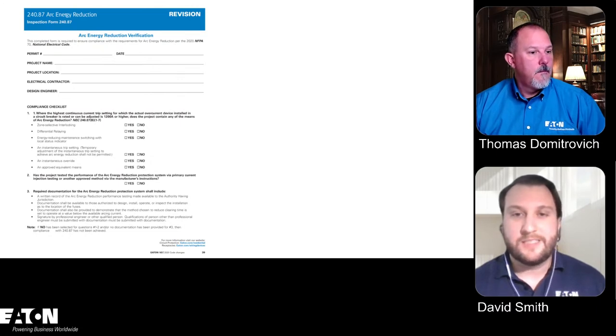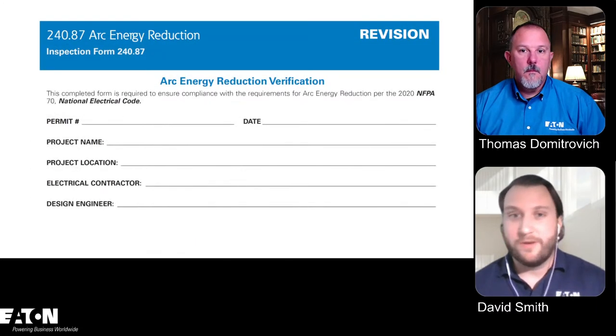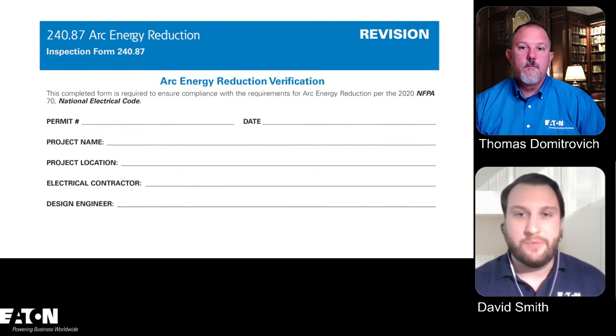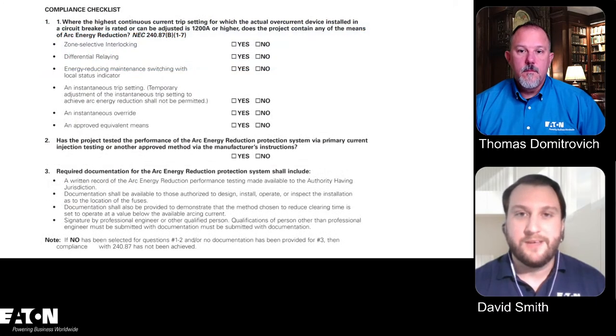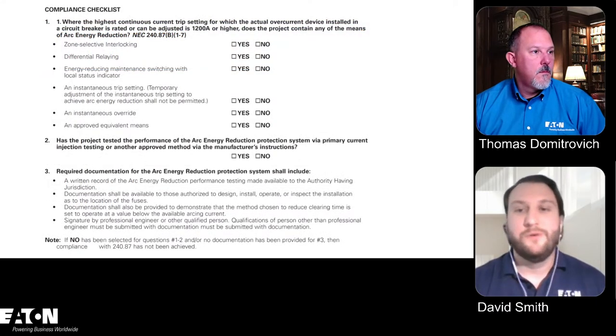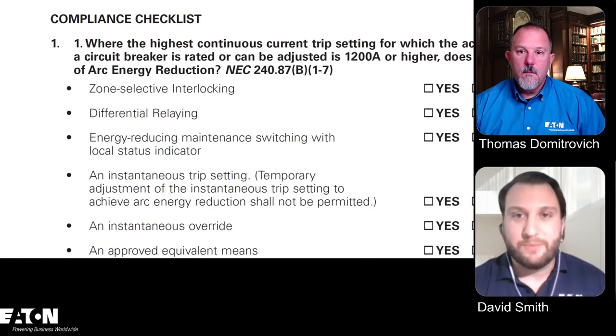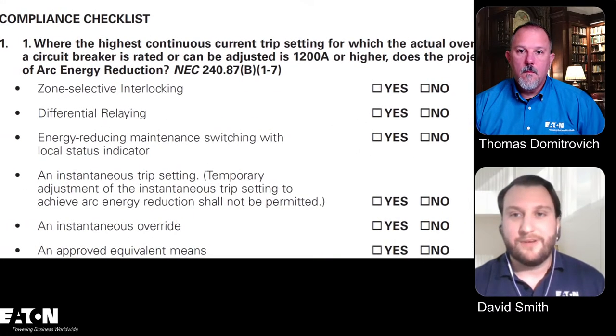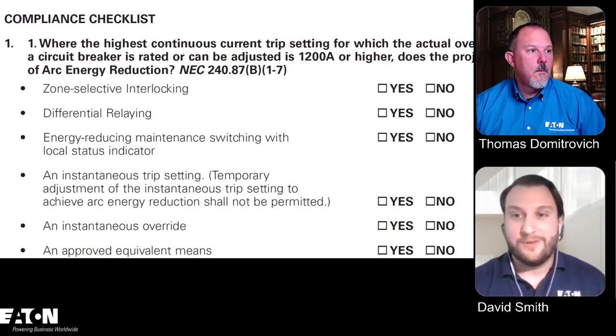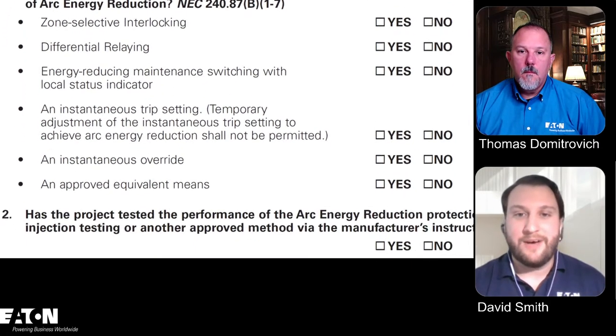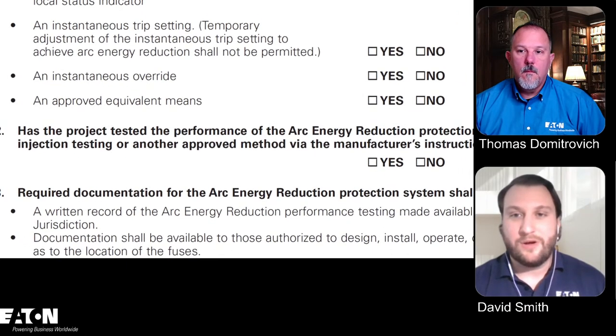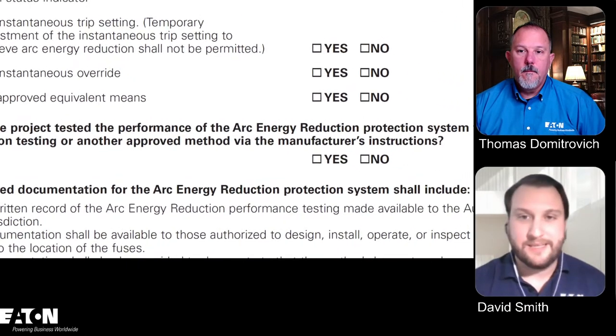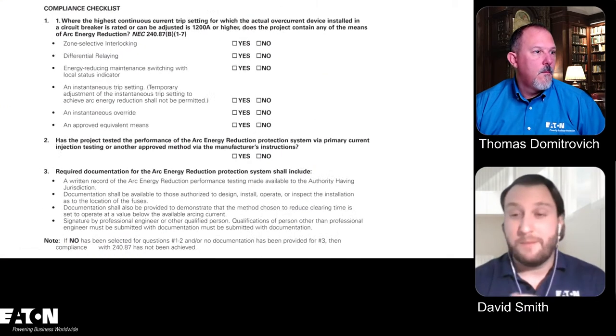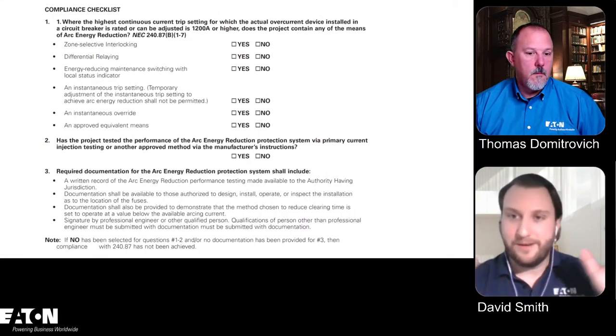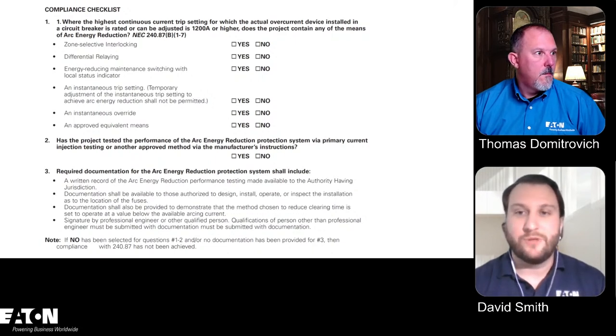And so if we go to the next slide here, it'll just go over the normal stuff: the permit number, the date, project name, everything that you would need when it comes to the inspection form of 240.87, and then the compliance checklist. Of any of these things for number one, do you have a particular solution that covers this? All you're going to have to do is check one of them. And then scrolling down, has the project gone under performance testing, particularly primary current injection testing or some other means that is cleared by the manufacturer, which we'll get to.